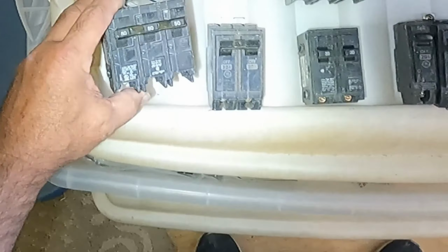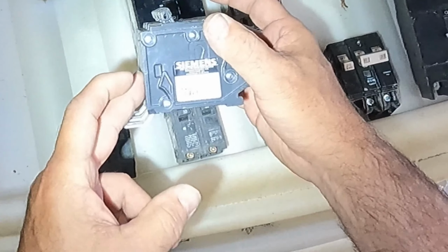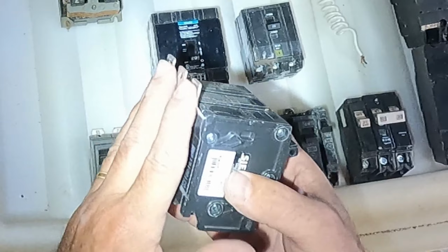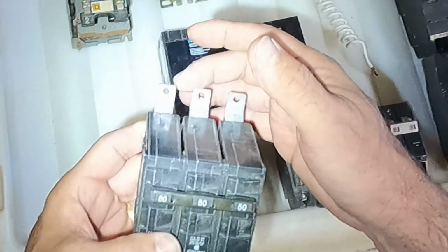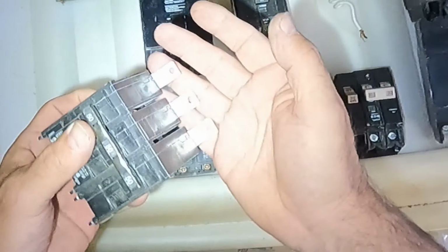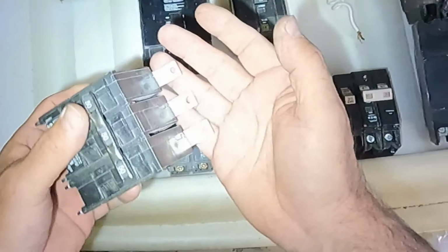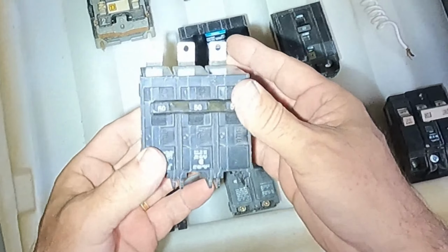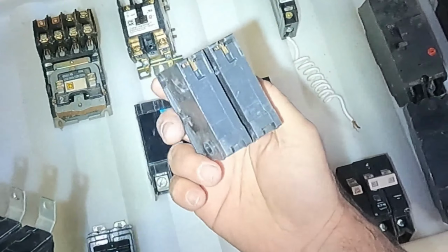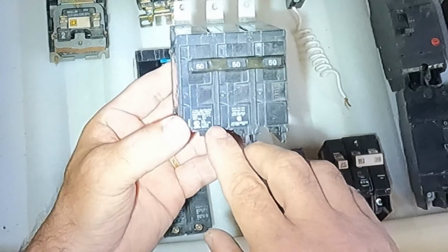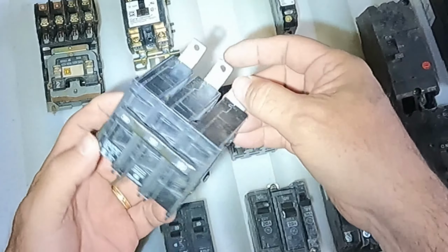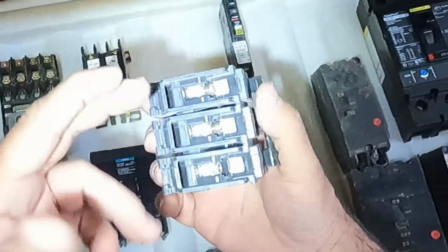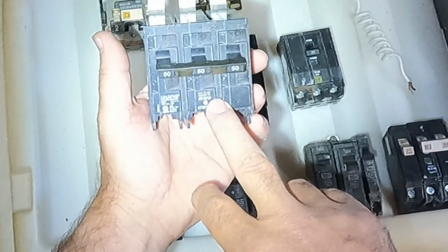So here I have a 3-pole Siemens breaker. This is a bolt-on breaker. I believe it's a BQD is what it's called. These are for more of an industrial situation, so these are rated a little bit higher because these actually get screwed down to the bus bar, as you can see, as opposed to just plugging in like you have at your home in a load center. And if we look at it, this is not rated for DC. Even though you can simply connect to here, and you've got your terminals here, and you've got a 50 amp breaker, this is not rated for DC.